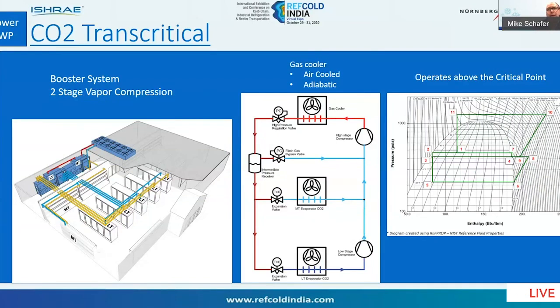The system also has a high pressure regulating valve, which is going to try to regulate the outlet temperature and pressure based on the ambient conditions to try to maintain the highest refrigeration effect and efficiency. During the subcritical operation, it will be designed and controlled to maintain a certain amount of subcooling. And then, of course, this has an intermediate pressure receiver or a flash tank. Also of note, the system would have electronic expansion valves.